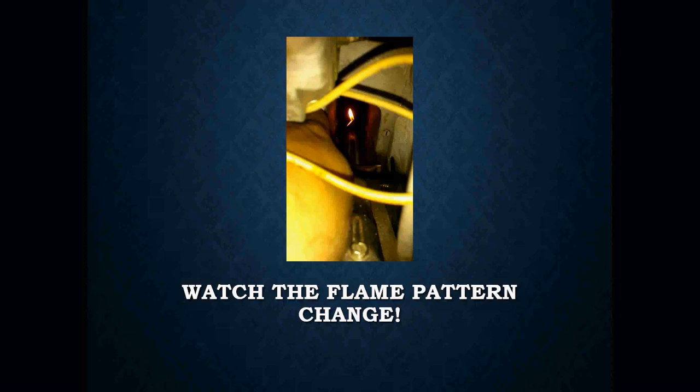The reason why I say to do it that way is because there are sometimes hairline cracks in the heat exchanger that will not necessarily be opened enough to allow any sort of air to make its way inside the heat exchanger. So we have to allow the metal to expand a little bit. And when that metal expands, the crack is going to widen. And when that widening happens, you'll actually see the flame pattern change.